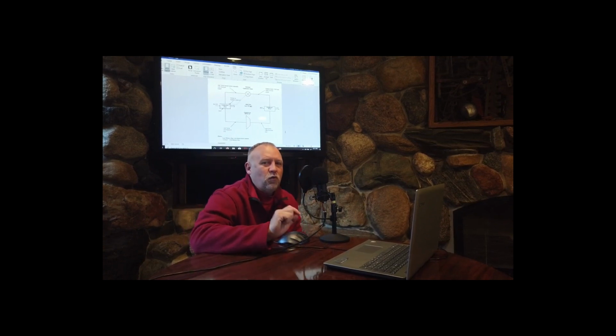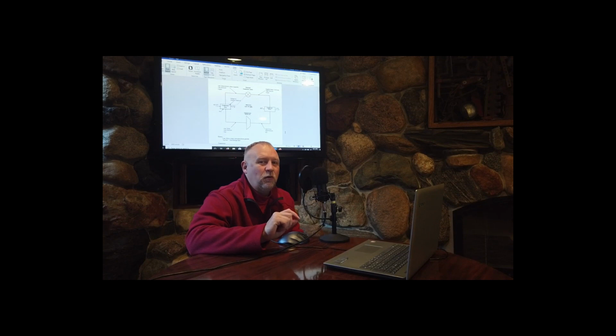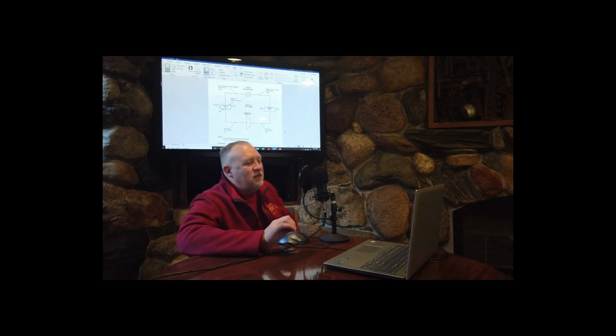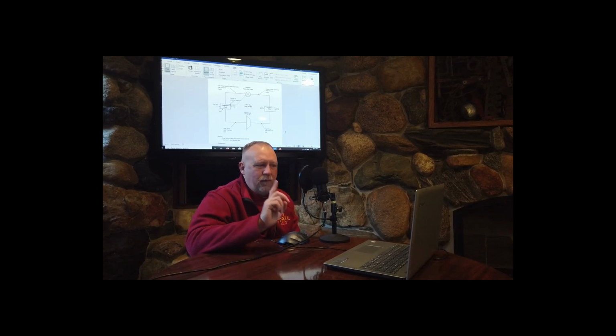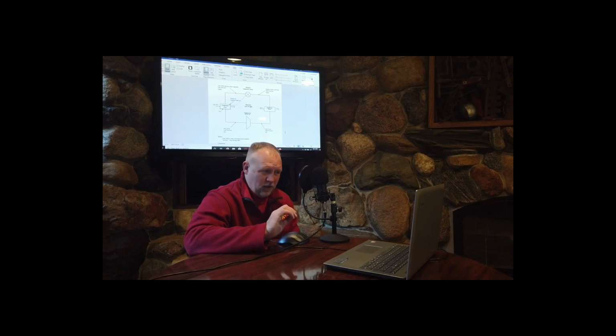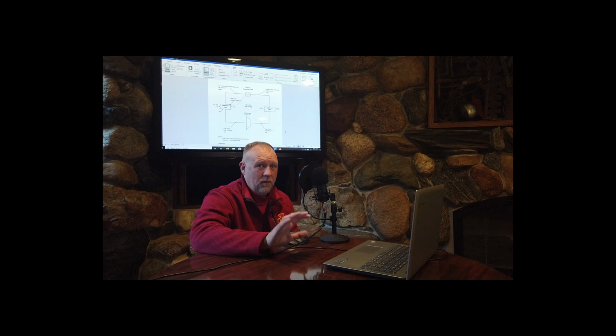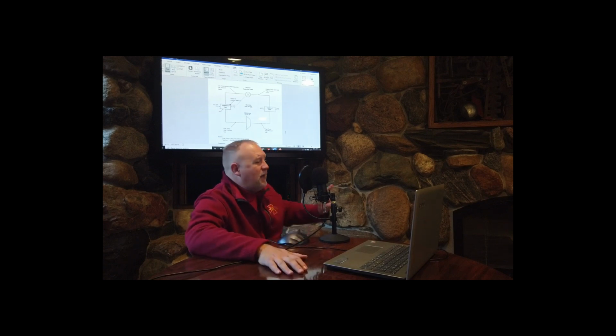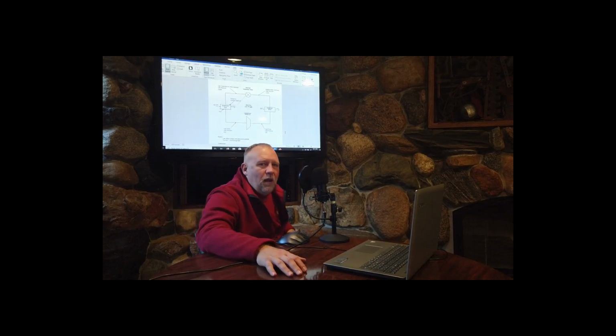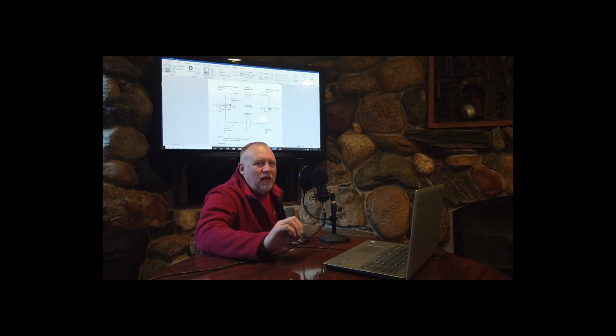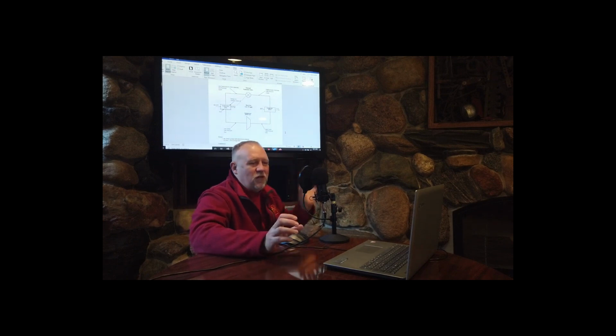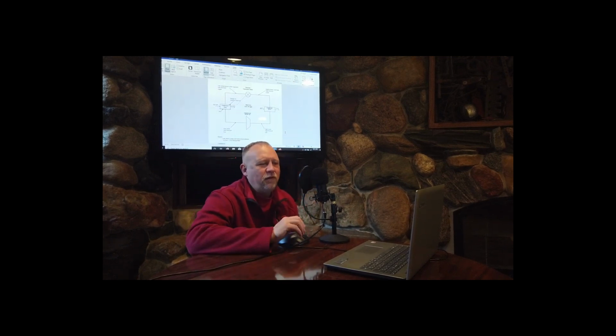Well, we don't just remove sensible energy from this return airstream. We also remove latent energy. This coil has to be colder than the dew point. Important point here, write this down. The temperature of the evaporator coil has to be at or below the desired dew point temperature that we want in the space, in the room, in the building, in the people space. Because, notice this drip pan, as this return air hits that coil, it's going to condense some of that moisture. And what that drip pan does is it catches that moisture as it falls off the evaporator and then takes it to a floor drain.